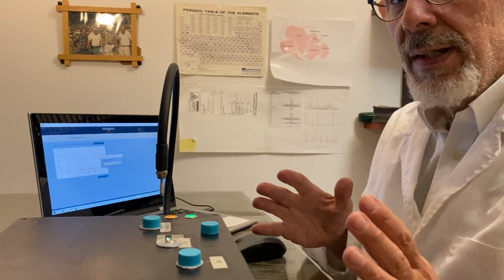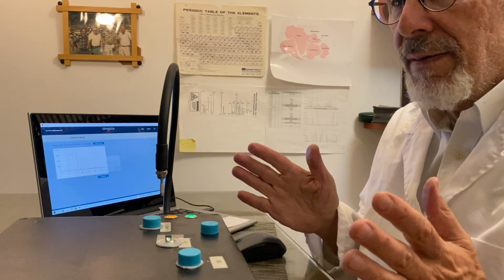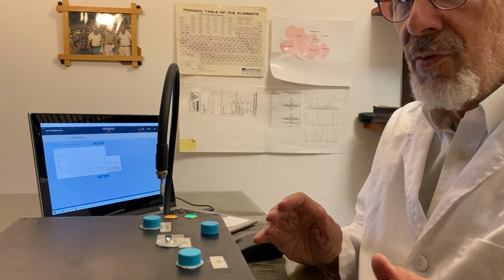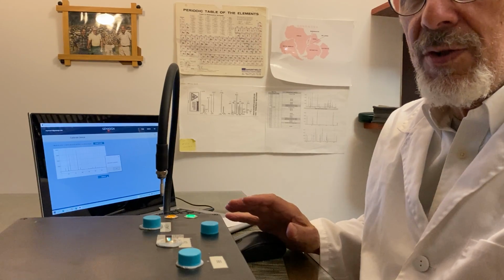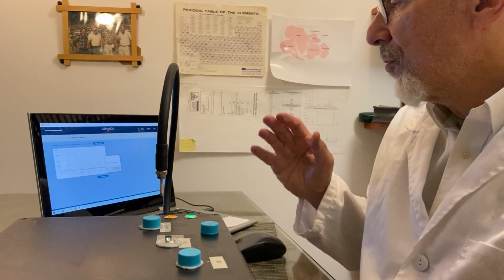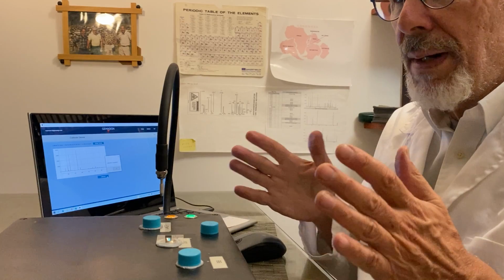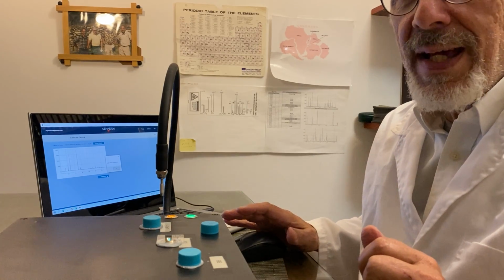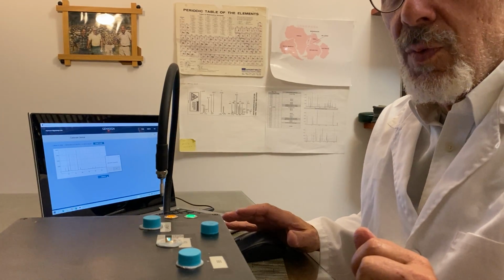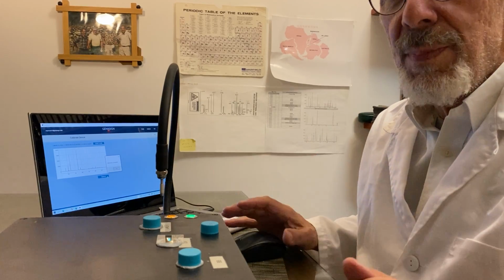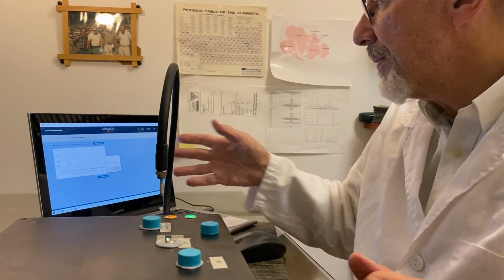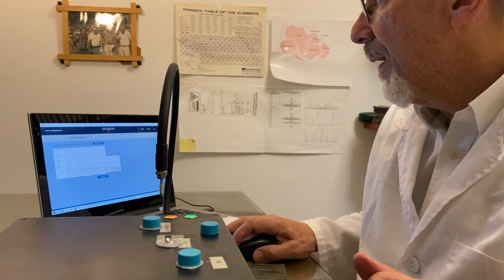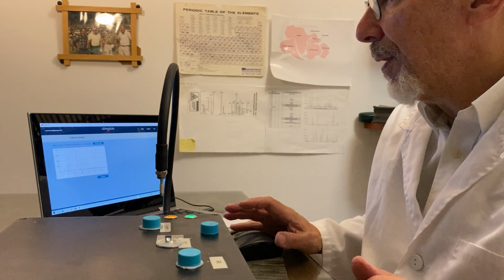What it's doing is there are about 25 to 30 atomic lines in the argon-mercury spectra. It's adjusting them so they come out within about 2 to 3/10 of a nanometer to where they're supposed to come out. Okay, it says calibration complete. I can check the calibration.